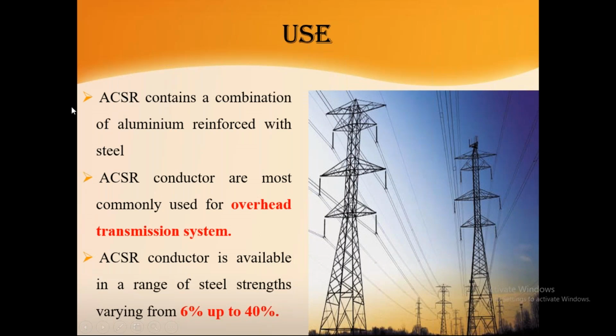Compared to the last two conductors, ACSR has more mechanical strength. Why? Because we are placing steel in the inner core, which gives additional strength to the conductor. That's why this type of conductor is mostly used in overhead transmission lines, and it is capable of carrying more voltage.